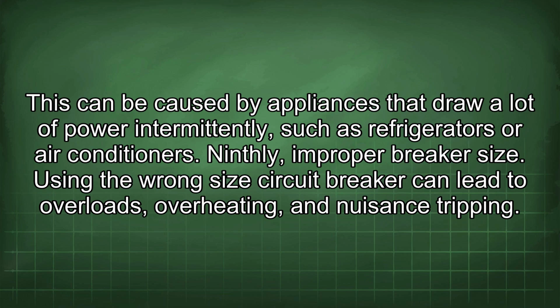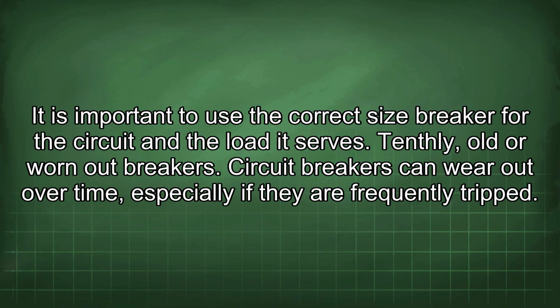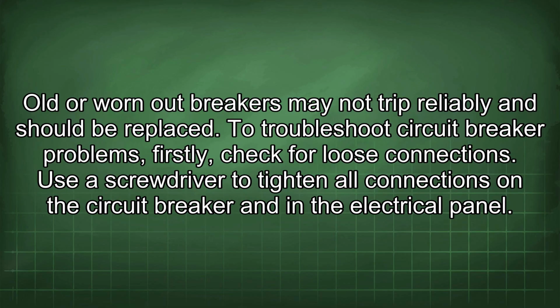Ninthly, improper breaker size. Using the wrong size circuit breaker can lead to overloads, overheating, and nuisance tripping. It is important to use the correct size breaker for the circuit and the load it serves. Tenthly, old or worn-out breakers. Circuit breakers can wear out over time, especially if they are frequently tripped. Old or worn-out breakers may not trip reliably and should be replaced.